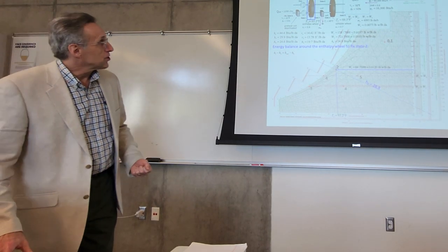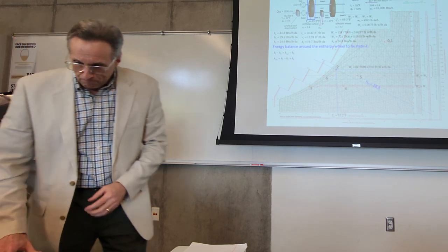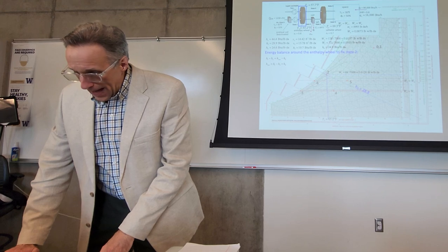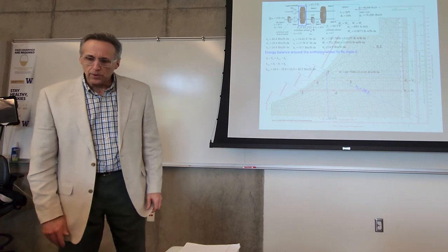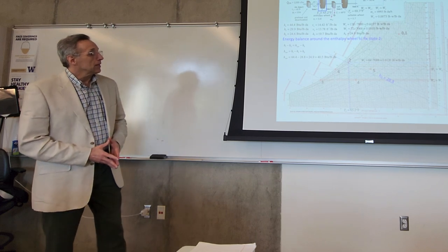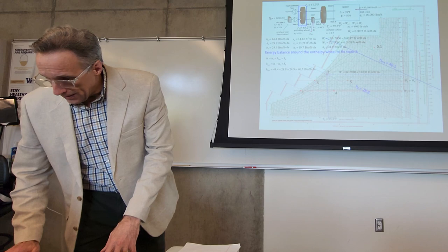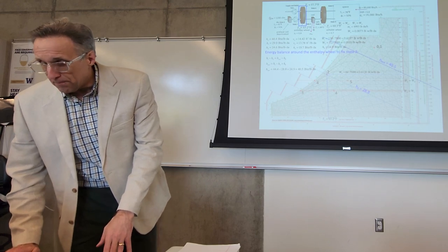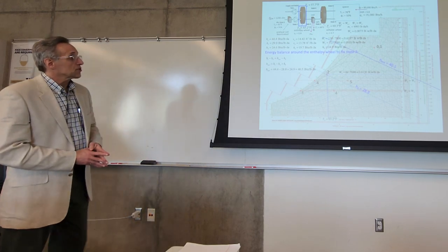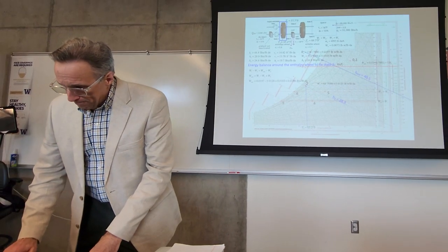So there's our moisture. We can make a note of what the moisture is. And then we can calculate our enthalpy out, which we really don't need to figure out the cooling load, but this just brings completeness to our analysis. H out, we're going to be up closer now to the outside air. This is our exhaust.